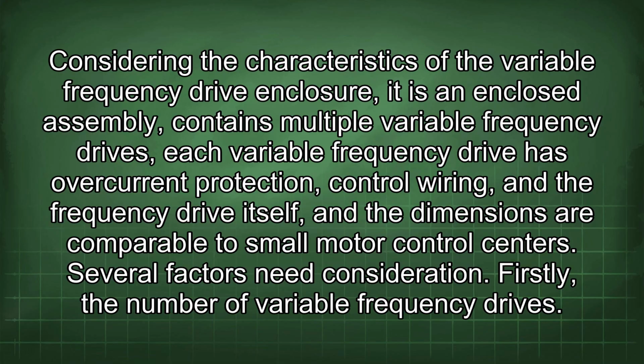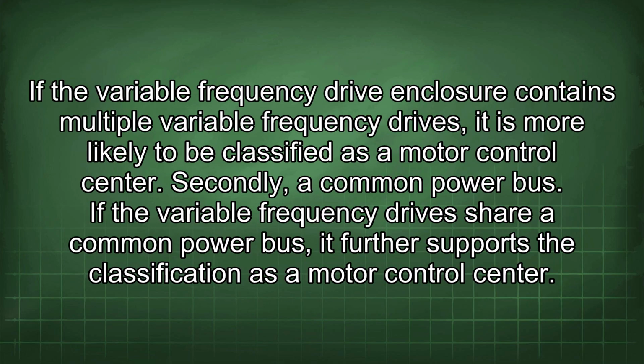It contains multiple variable frequency drives. Each variable frequency drive has overcurrent protection, control wiring, and the frequency drive itself, and the dimensions are comparable to small motor control centers. Several factors need consideration. Firstly, the number of variable frequency drives. If the variable frequency drive enclosure contains multiple variable frequency drives, it is more likely to be classified as a motor control center. Secondly, a common power bus.